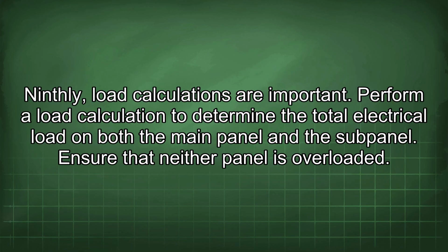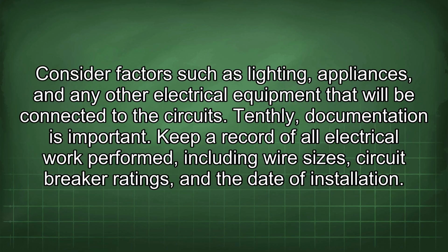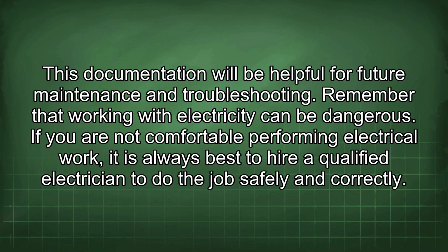Ninthly, load calculations are important. Perform a load calculation to determine the total electrical load on both the main panel and the subpanel. Ensure that neither panel is overloaded. Consider factors such as lighting, appliances, and any other electrical equipment that will be connected to the circuits. Tenthly, documentation is important. Keep a record of all electrical work performed, including wire sizes, circuit breaker ratings, and the date of installation. This documentation will be helpful for future maintenance and troubleshooting.